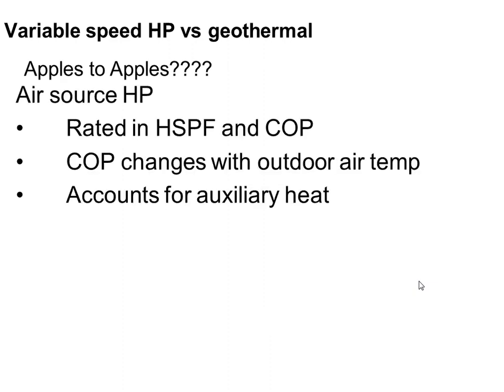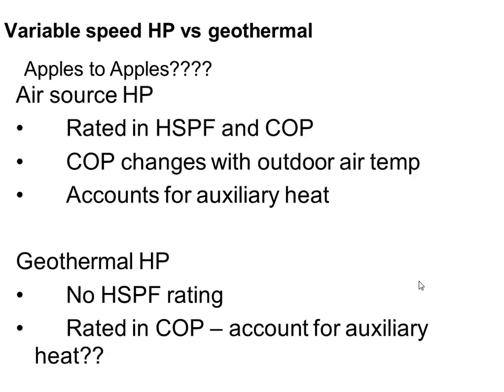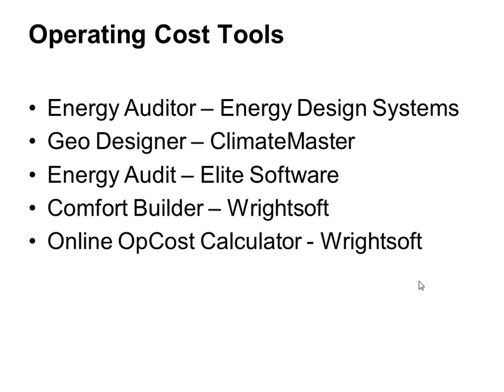If you want to compare to a geo system, you can do that. We got to use the COP numbers instead of the HSPF numbers. The other thing that comes into play is that the air source guys account for auxiliary heat in their efficiency numbers. The geothermal guys don't, so it's not really fair. It's not really apples to apples, but we can still go ahead and try to use it as a comparison.